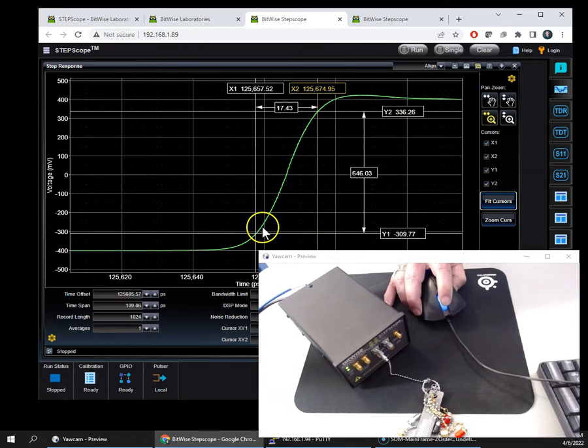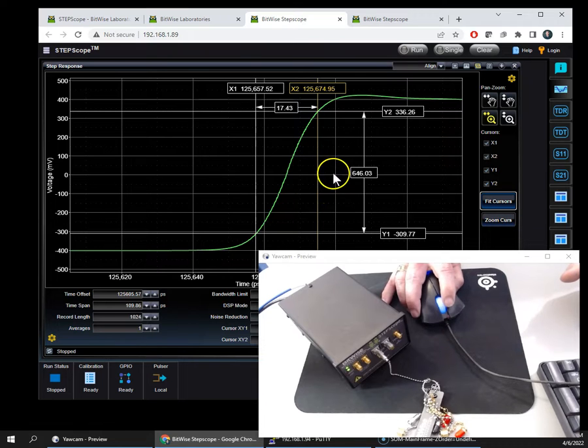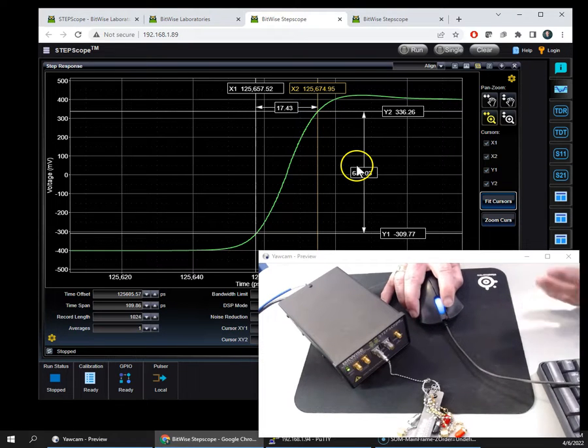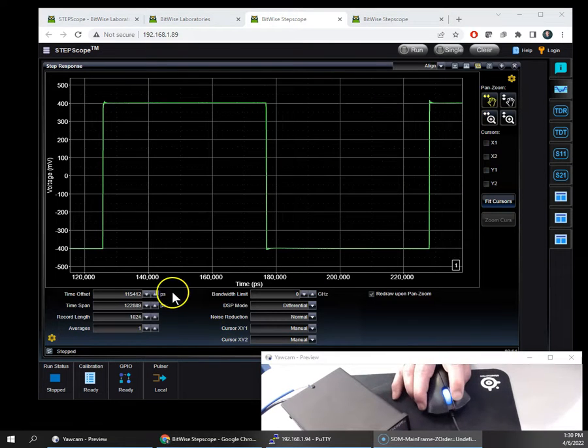the instrument. So that gives you a feel for the bandwidth inside the sampler and the pulser inside the device when making TDR measurements. That's not the same edge as you get outside the machine. Outside the unit, we specify 20 picoseconds, 10-90. It's a little bit faster than that, but that's without any kind of losses. You would then also have losses of your system when doing reflection measurements or transmission measurements as well. Back to the full square wave.